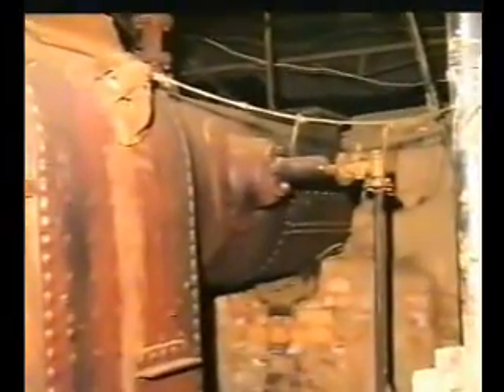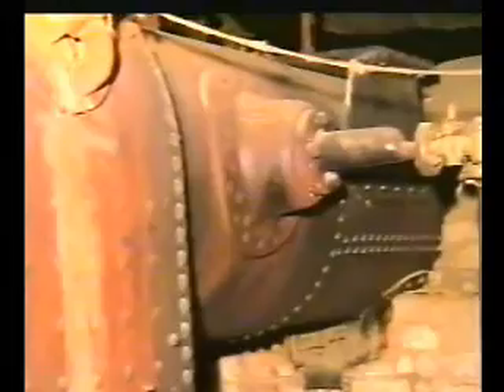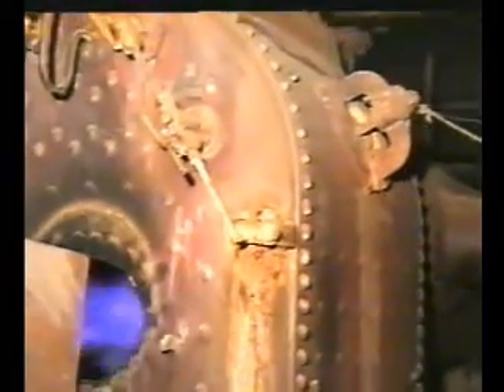This is a very small loco-type boiler of half ton per hour capacity required for only parboiling purpose. With the help of a suitable burner, this boiler has been converted for firing with the producer gas. Besides high thermal efficiency, with this modified system, no big chimney or furnace is required, as there is no ash at all. Further, frequent stoppage for ash removal and therefore laborers for this purpose are not required.